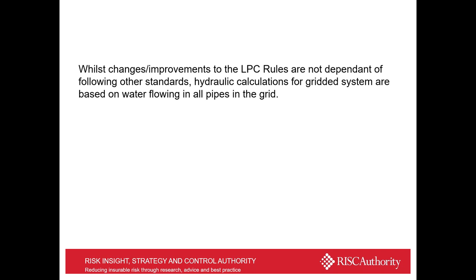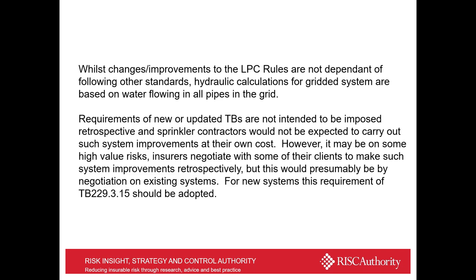With regards to technical bulletin updates, while changes and improvements are not dependent on following other standards, the question was raised about what other standards say. Hydraulic calculations for gridded systems are based on water flowing in all parts of the grid. The requirements of the updated technical bulletins are not intended to be imposed retrospectively — sprinkler contractors would not be expected to carry out such system improvements at their own cost. However, on some high-value risks, insurers may negotiate with clients to make system improvements retrospectively, by negotiation. For newer systems, the requirements of TB229 3.15 should be adopted.